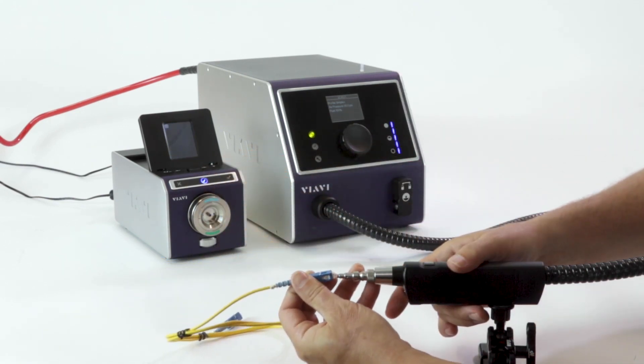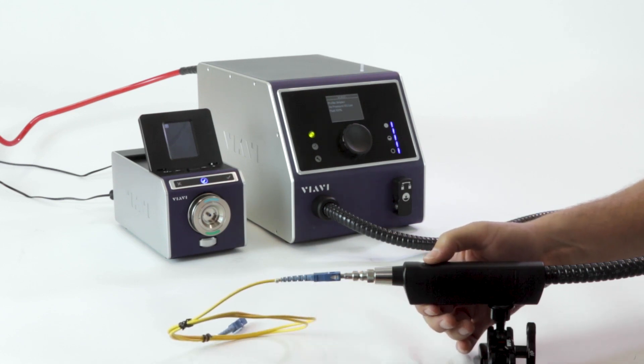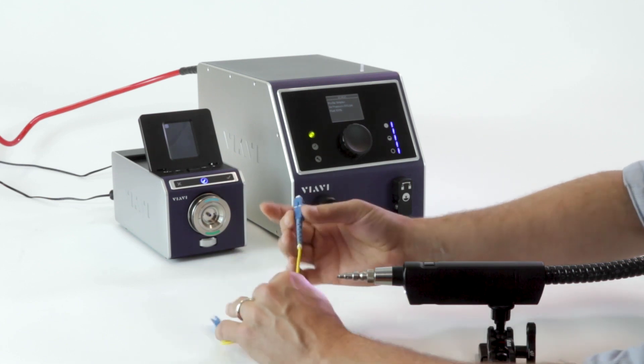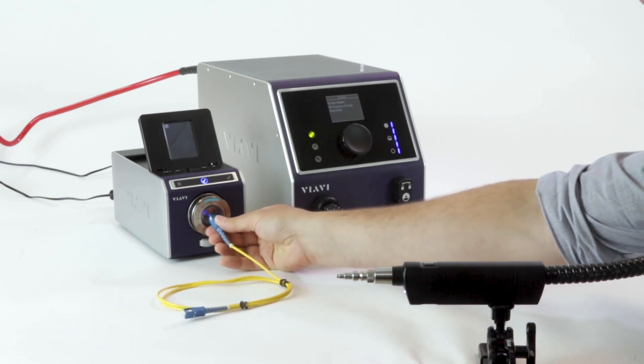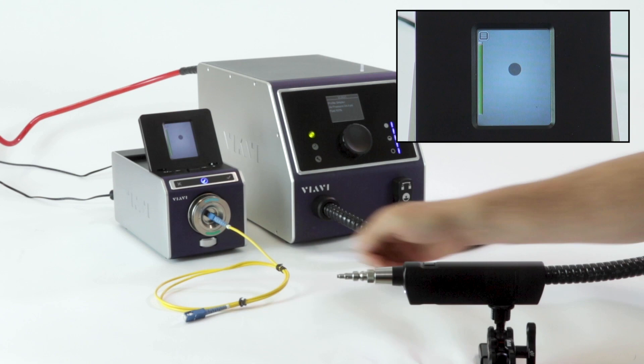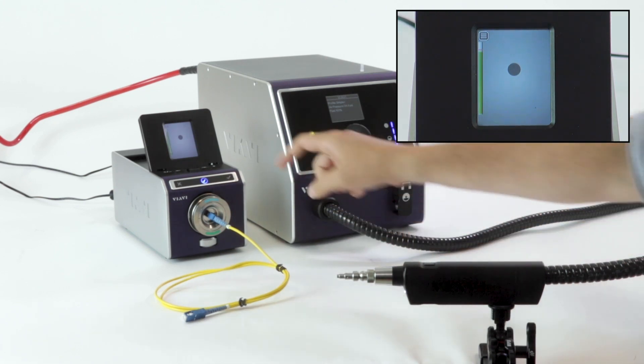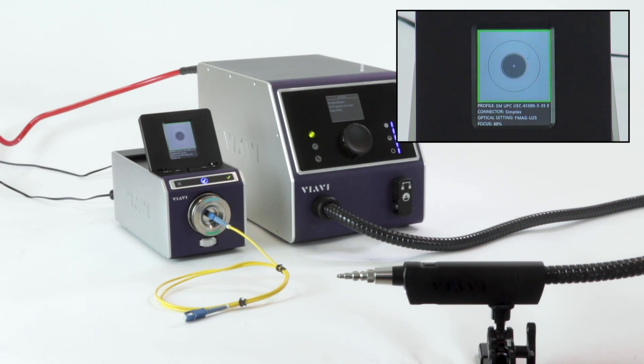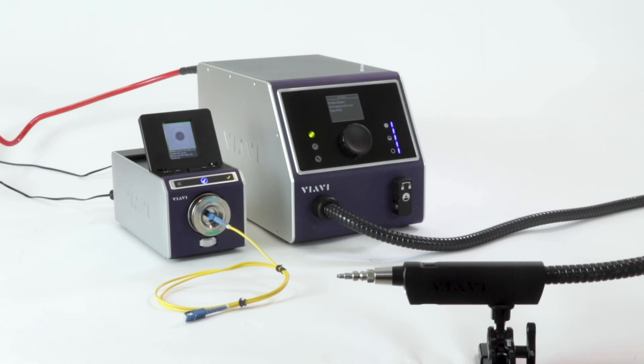We'll insert that into the Clean Blast Pro, give it a clean, and now let's check that again. Now you can see that it's pristine. If we were at the final stage of production, we'd want to use our pass-fail analysis to generate a pass-fail test and also a certification report, so we can send it to the customer. That's a summary of the cleaning process for a simplex patch cord.